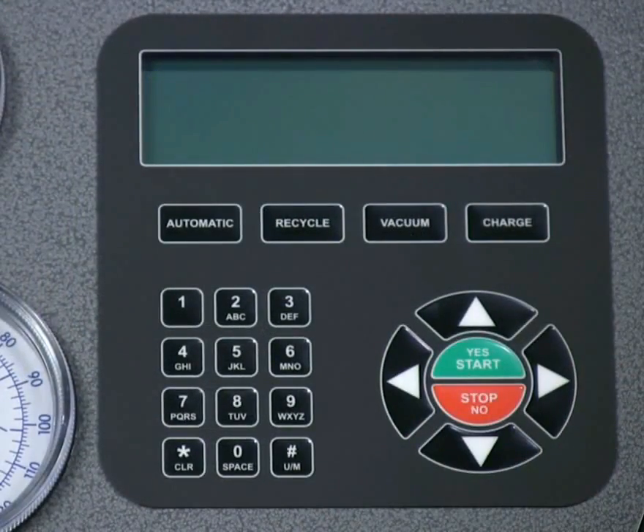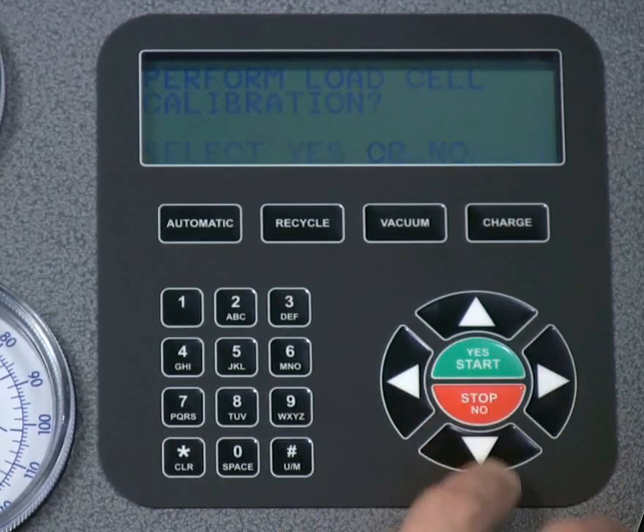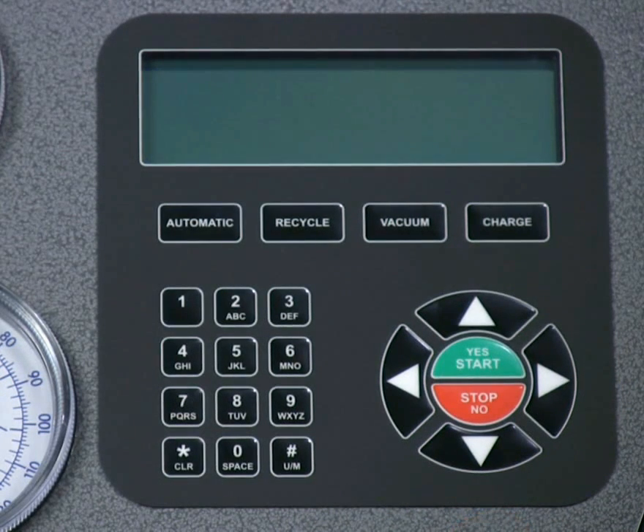During the calibration check, the screen will go blank for about 30 seconds. This is normal. Make sure you do not disturb the machine at this time. The LCD screen will indicate if the machine is in calibration. Press the green Yes button to continue to the next screen. If the unit fails the calibration check, the RHS980 requires a load cell calibration. Please contact RTI Technologies directly at 1-800-468-2321. Press extension 1 for assistance with load cell calibration.